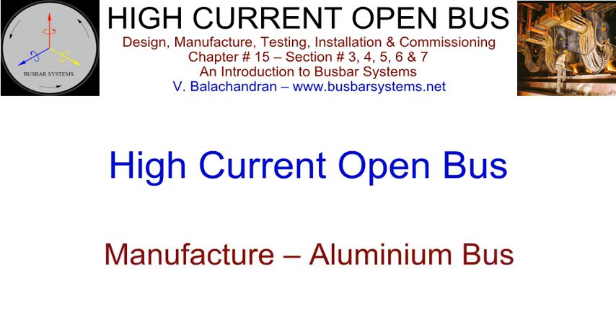Aluminium. Aluminium busbars for high current applications are manufactured from cast aluminium bars conforming to grade 1350. These are available in maximum cross-sections of 2 feet wide, 6 inches thick and 20 feet long, weighing approximately 2 tons. A custom-built machining facility is required for handling such heavy bars, cutting them to size, milling the surface, and drilling. Metal inert gas welding is extensively used for the fabrication of busbars.